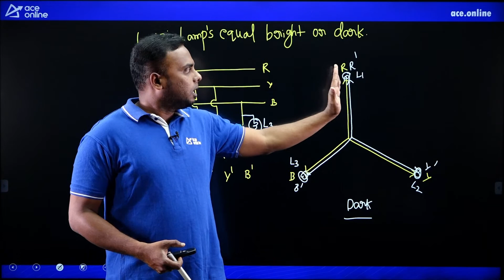Suppose frequency of alternator is different than bus bar. R,Y,B rotating in space here at synchronous speed, R dash, Y dash, B dash also rotating at synchronous speed. If frequency is more, meaning speed of alternator is more, then R dash, Y dash speed also increases. So after some time R dash will move away from R, maybe at one instant both in phase, but after some time R dash will go away from R. Then slowly voltage increases, lamp becomes bright, then again comes near dark.